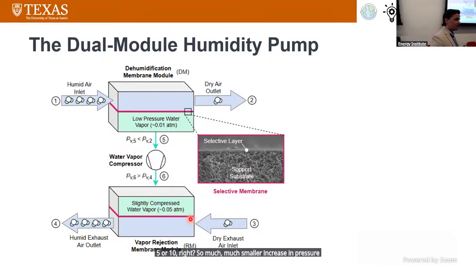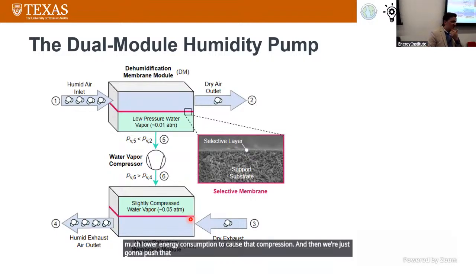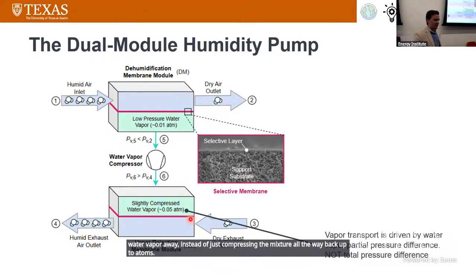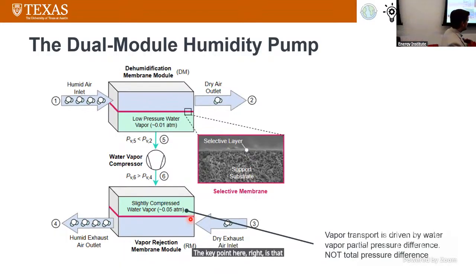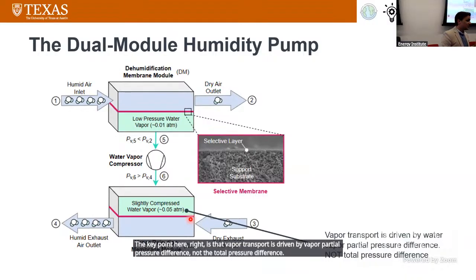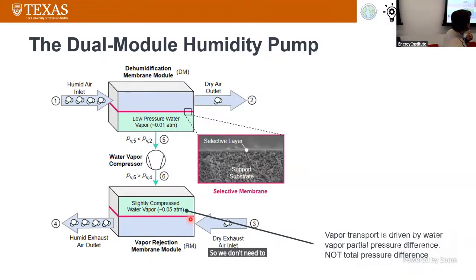So we get much lower energy consumption to cause that compression, and then we just push that water vapor across the selective membrane, which carries the water vapor away instead of compressing the mixture all the way back up to atmosphere. The key point is that vapor transport is driven by vapor partial pressure difference, not total pressure difference—so we don't need to compress that water vapor mixture at state 6 all the way back up to atmospheric pressure.